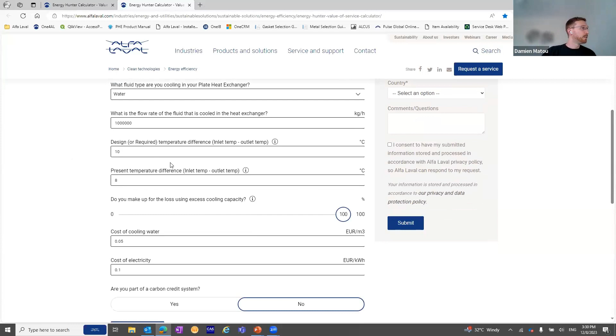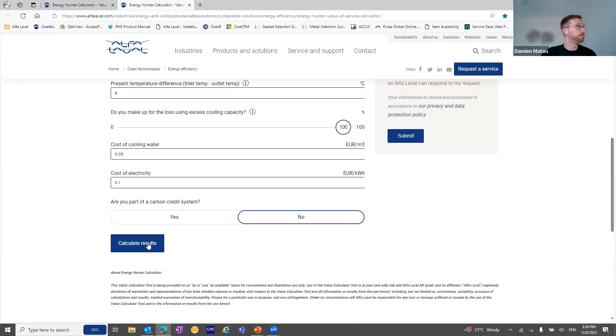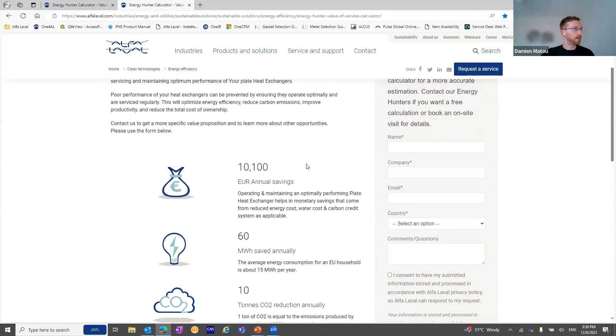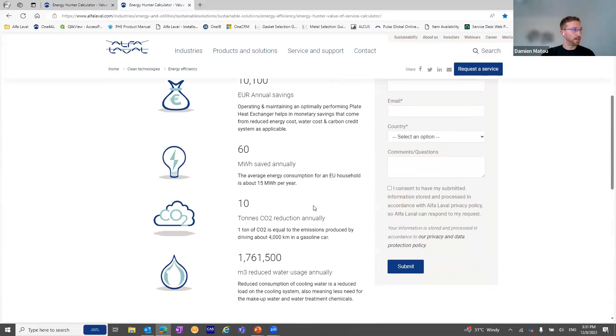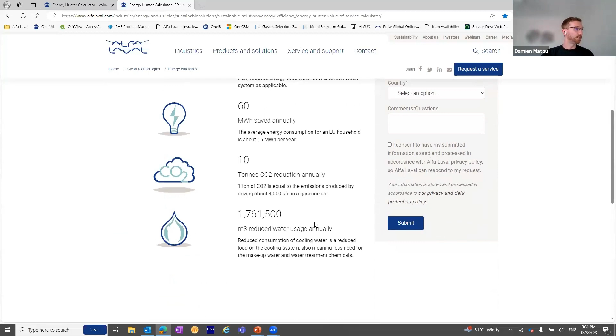Then if you make up the loss using excess cooling capacity, for example additional chiller capacity or increasing the cooling water circulation, you just enter the cost of water and the cost of electricity, and if you are part of any carbon credit system like they have in Europe. Then you get the numbers here: the saving in euros, electricity saving, CO2 reduction, and also the water reduction saving.